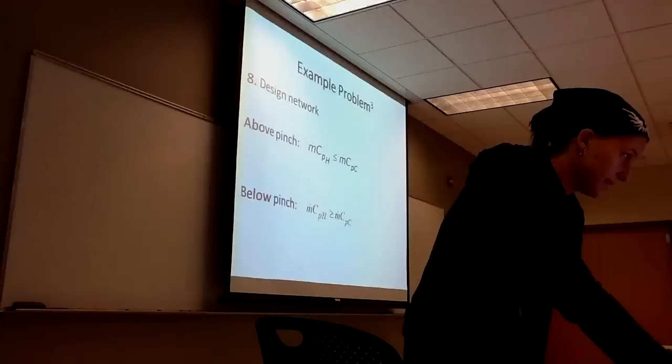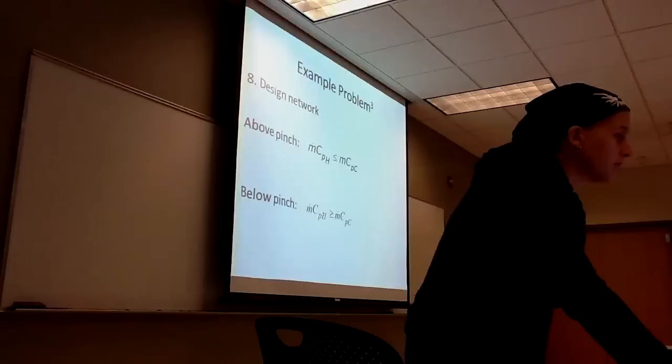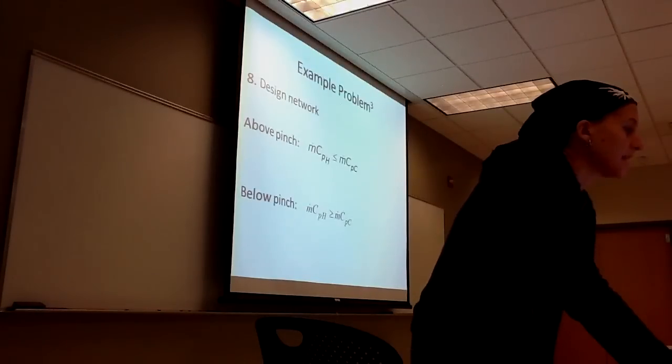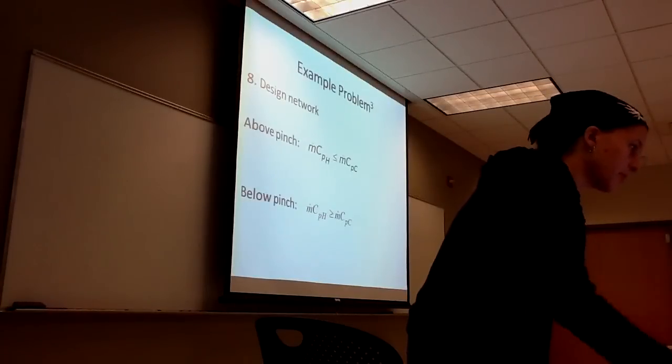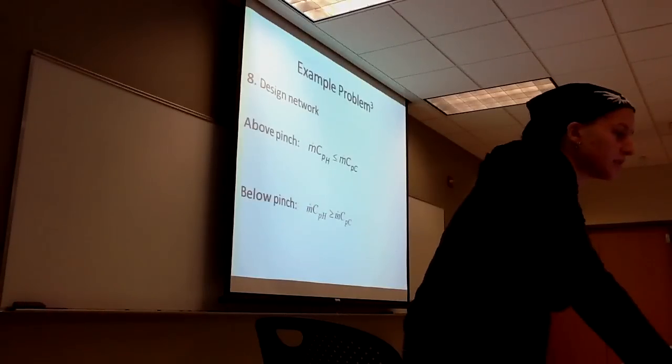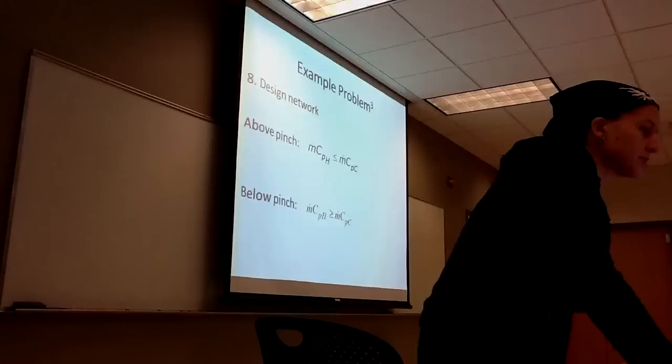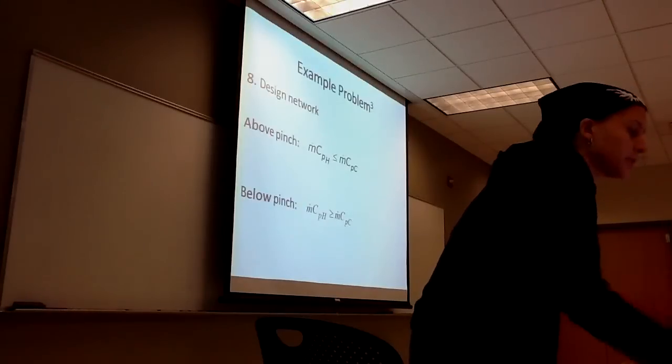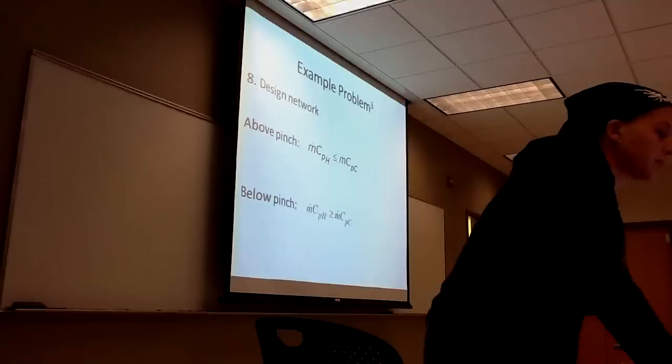Now, you can design the network. Keep in mind, above the pinch, your MCP must be less in the hot region than it is for the cold stream. And below the pinch is the opposite. The hot stream MCP must be bigger than the cold stream MCP.